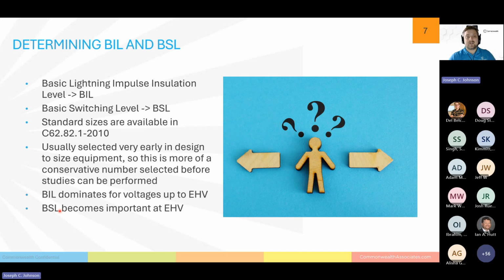These are usually selected very early in the design, and that's to size the equipment. Sometimes we don't even necessarily have time to really dig in on these studies. And with the way that the industry is going and having lead time be about the most important thing now, even cases where it's just shut up and take my money, get it done as fast as you can. That's a lot of the cases we're seeing. We're generally going a little bit more conservative just to make sure that we don't have any surprises later in the project and have to reorder something.